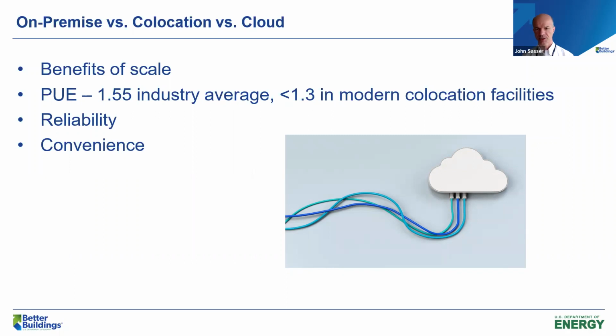They have some advantages. They work very closely with server manufacturers to build servers in certain ways, and often have flexibility in how they condition those servers, operating at very high temperatures and humidities that many of our customers would not allow. Still, in modern co-location facilities an average annual PUE of 1.3 is very common, and we have some that are much more efficient. Our average PUE across our portfolio is 1.23, and some are 1.15.